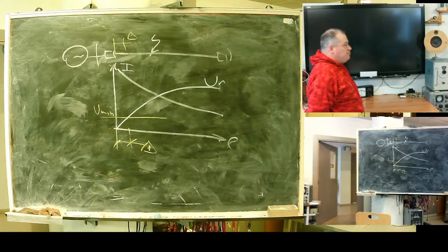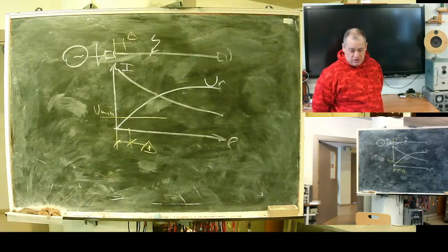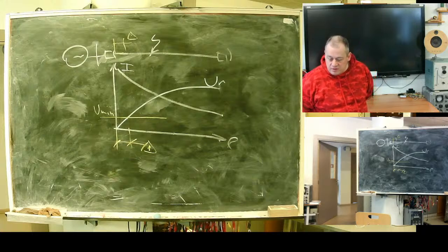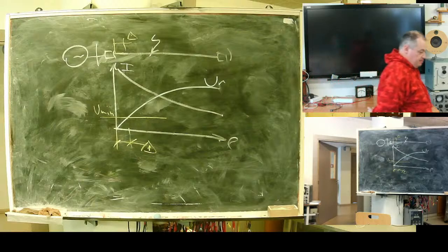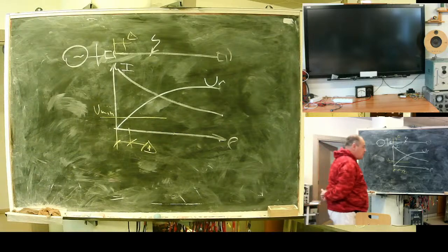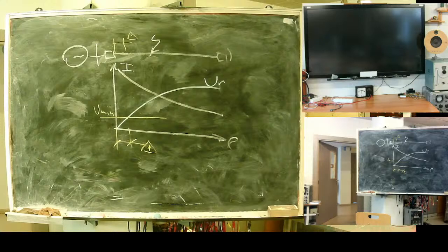In case AB voltage disappears or is lower than the operation threshold, contour remembers, it's a memory circuit, keeps for some time direction of C phase voltage. It's used to determine direction. So Gen 2 relays in reality become directed overcurrent relays.